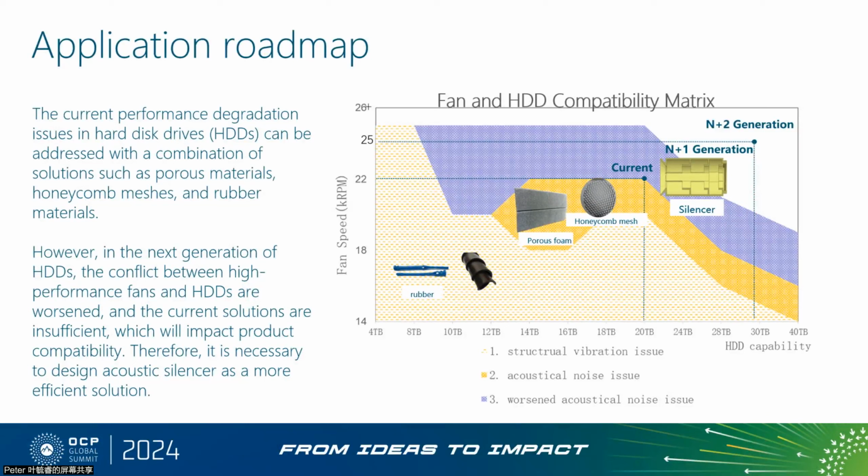The conflict between the need for high-performance fans and the susceptibility of HDDs to acoustical vibration has intensified. Current solutions, including porous foam and honeycomb mesh, are proving to be insufficient in the most extreme configurations, potentially impacting product compatibility and performance.